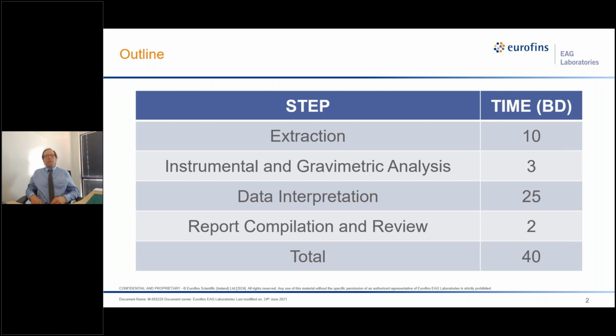Before we get started, I'm picking a representative project, right? We've got a reasonable extractables profile. There are things above the AET, so there's going to be some work to be done, but it's not a particularly complicated extractables profile. That can definitely have an influence. We're also assuming that we're going to do 3 extractions. This is an exhaustive device, but we're not having challenging issues like continuing NVR where it doesn't seem to be tapering off much. It's not a complicated material that may be degrading. So fairly simple that way. Those are the fringe cases. I'll discuss those a little bit towards the end.